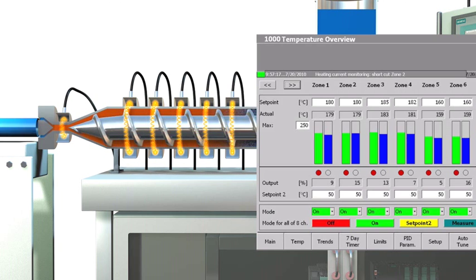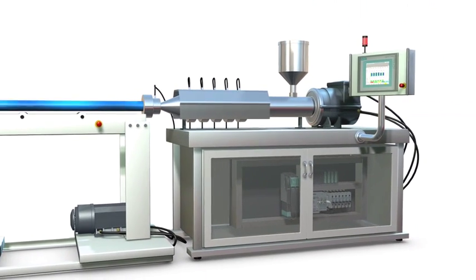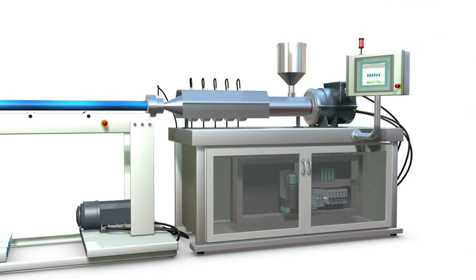If the temperature set point is exceeded, the heater bands are de-energized via the digital module and solid-state contactors and cooled as required. The control loop can be monitored and diagnosed with the TCP3000 temperature control software. This facilitates accurate tracking of all heater band states.